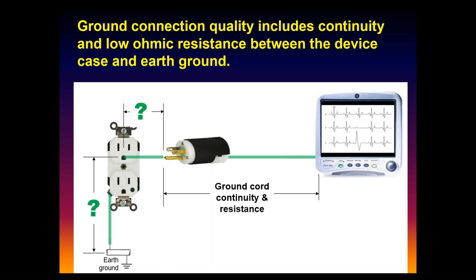There are two reasons why we have that ground connection, which we'll see in a minute. Outside your buildings or homes you can't see it anymore, but it's typically one or two 10-foot rods driven into the physical dirt, brought into your circuit panel, and that's where the neutral-ground bond occurs.